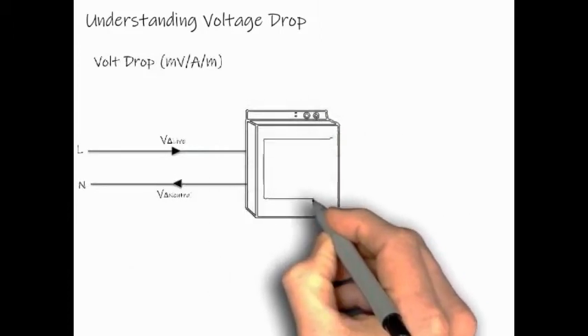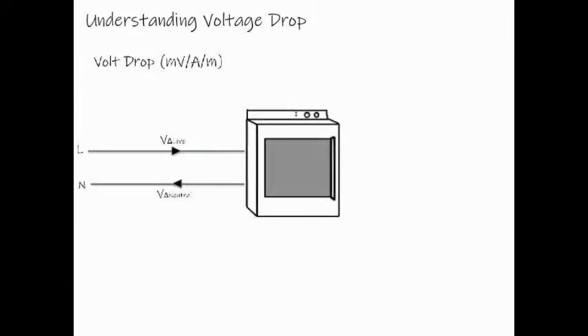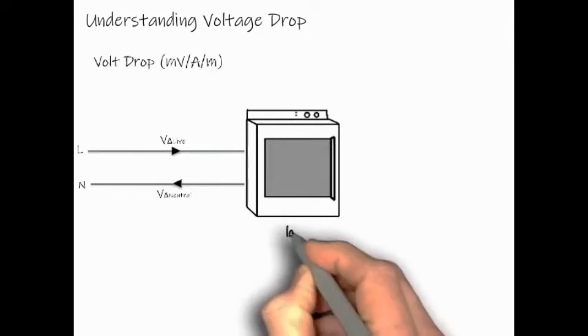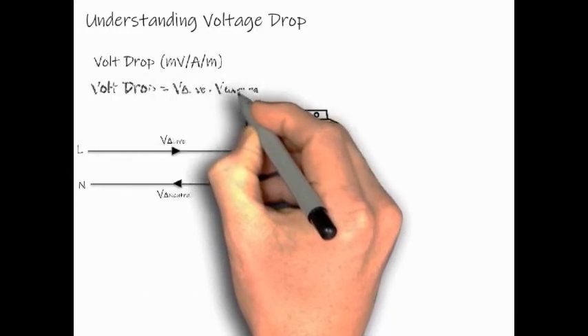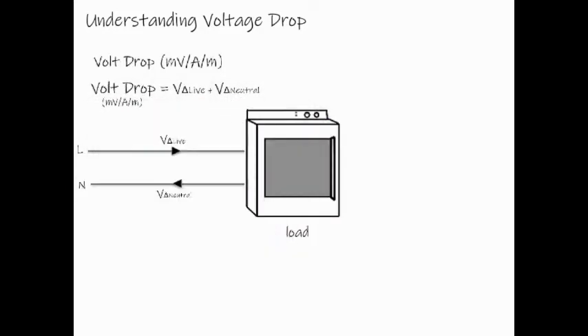For instance, a single phase load connected to a pair of live and neutral cable, the resistive voltage drop on the length per meter can be calculated by summing up the voltage drop in the live conductors as well as the neutral conductors. Therefore, the formula for voltage drop is equal to voltage drop on the live cable plus the voltage drop on the neutral cable.